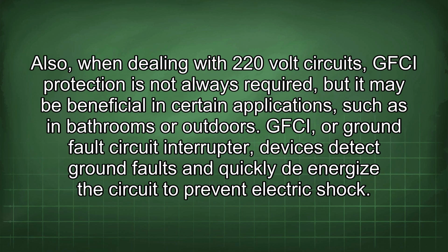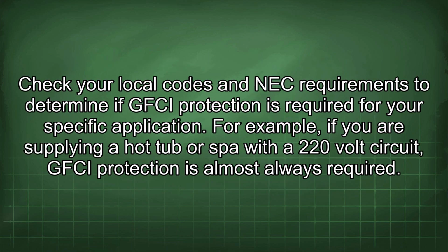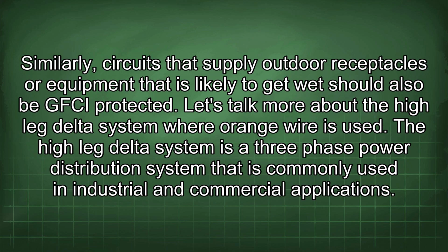Also, when dealing with 220-volt circuits, GFCI protection is not always required, but it may be beneficial in certain applications, such as in bathrooms or outdoors. GFCI, or ground fault circuit interrupter, devices detect ground faults and quickly de-energize the circuit to prevent electric shock. Check your local codes and NEC requirements to determine if GFCI protection is required for your specific application. For example, if you are supplying a hot tub or spa with a 220-volt circuit, GFCI protection is almost always required. Similarly, circuits that supply outdoor receptacles or equipment that is likely to get wet should also be GFCI protected.